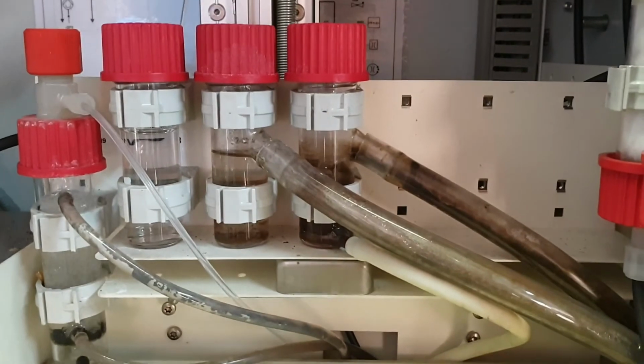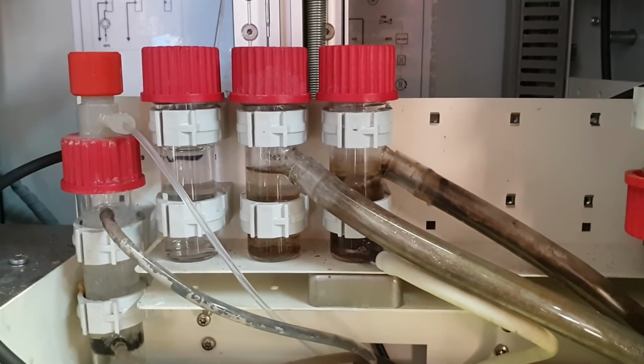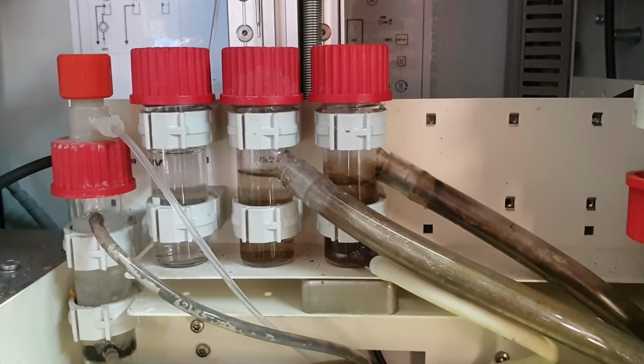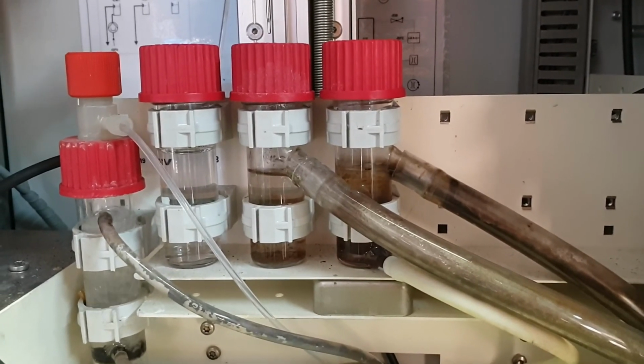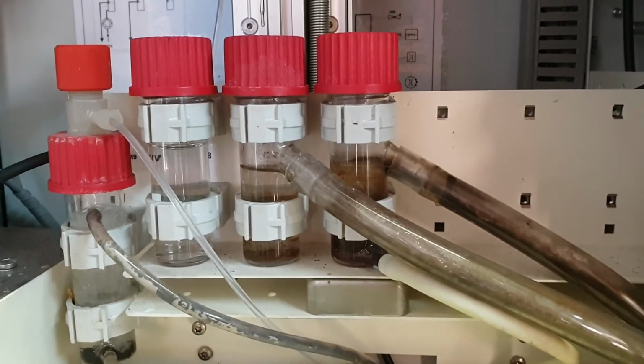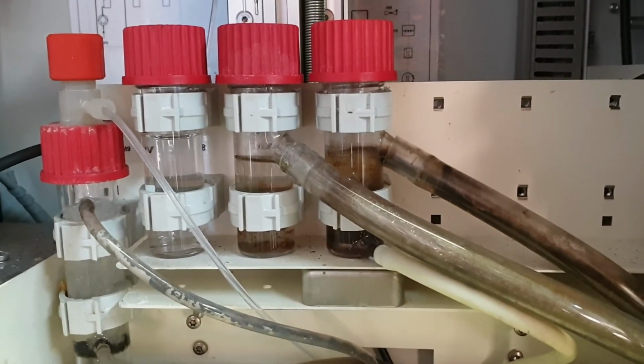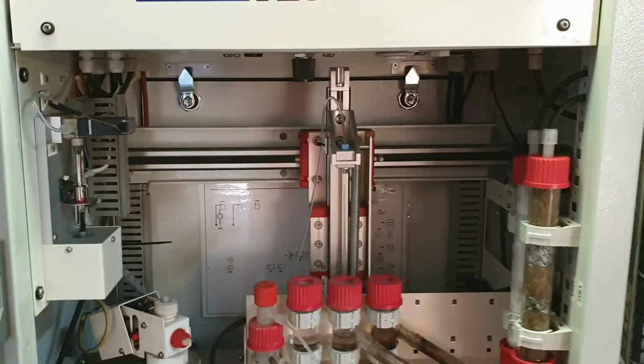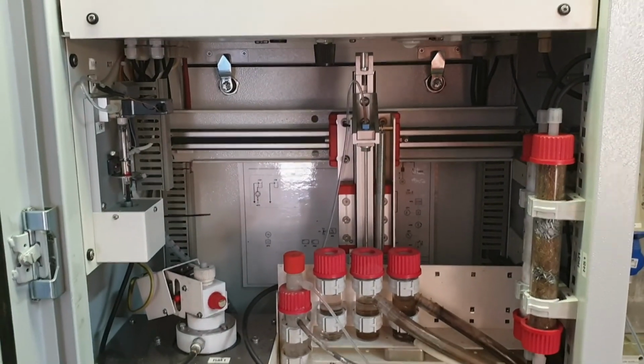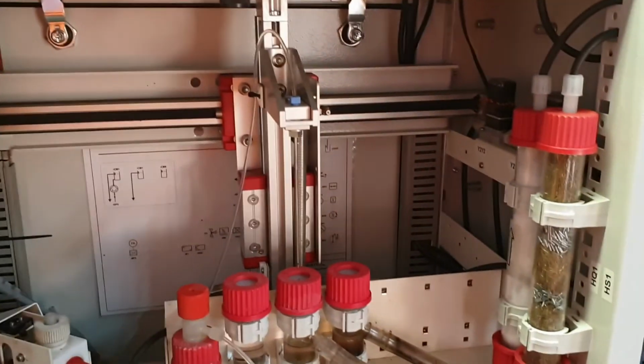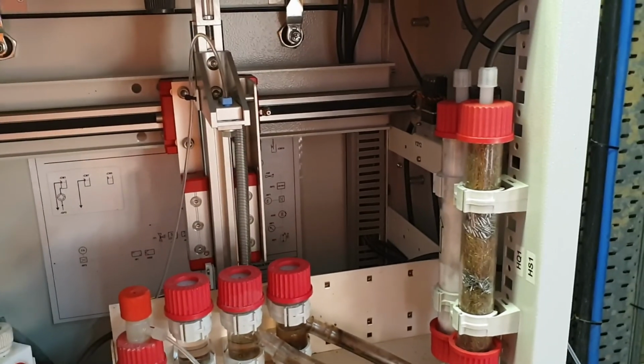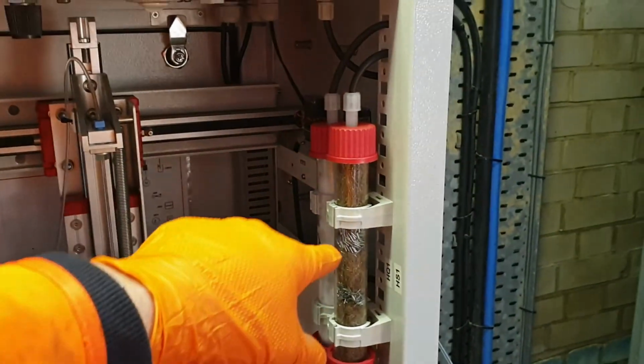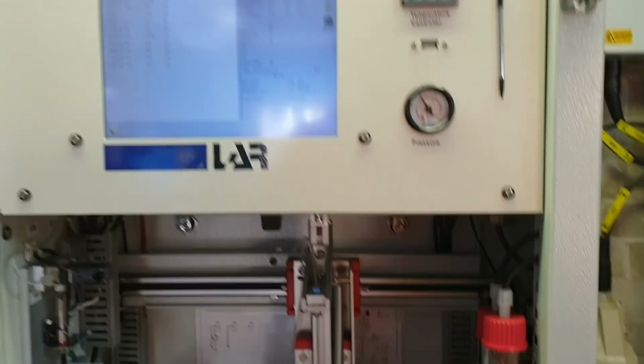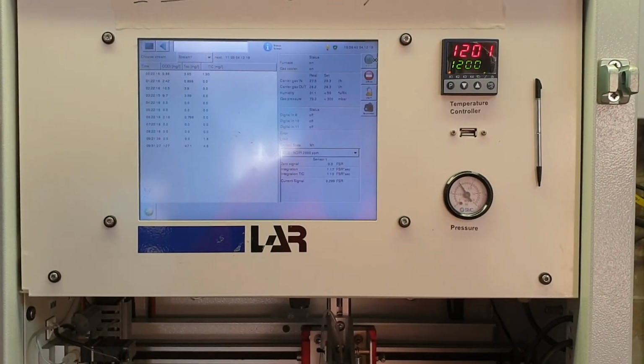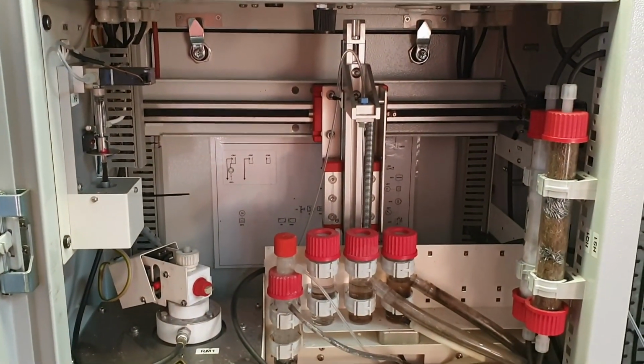So we're getting some bubbles through, because the line will be full of air. We should start filling up. There we go. So now it's overfilling that chamber, so we know we're getting sample going in, and it'll do an analysis on that chamber. Like I say, inject it into the furnace, inject it into the TIC, gets converted into a gas, which then goes up into the top and gets analysed by an IR bench from Edinburgh Sensors. Awesome. Right, see you in a minute.